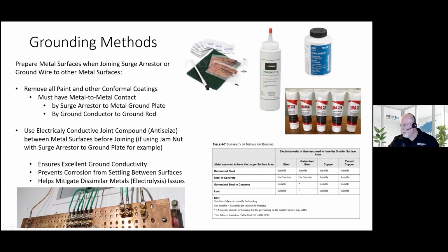So just the metal table here. Now, these are all just different examples of conductive joint compounds, or it could be Penetrox. Some people call it anti-seize. In the Coast Guard, we called it anti-seize, and it was molybdenum based, but it could be zinc based, it could be whatever. This is a PolyPhaser one, and it's copper based. And you can just see a little bit of the goo here on this example where somebody used it. Good practice.